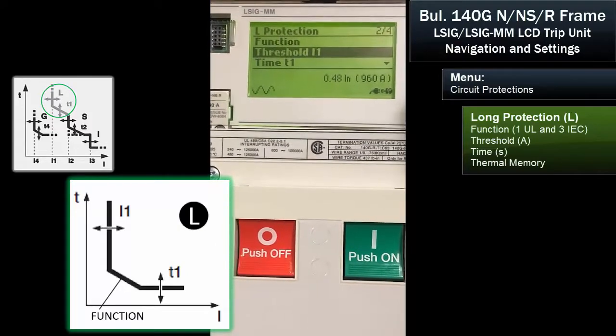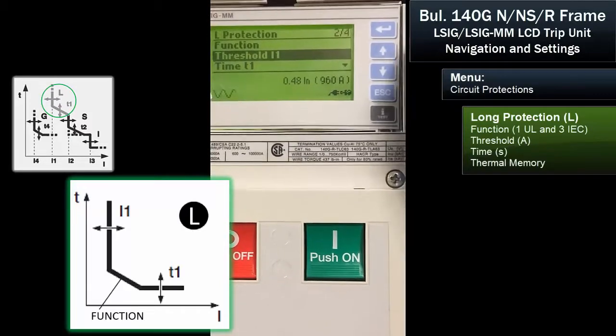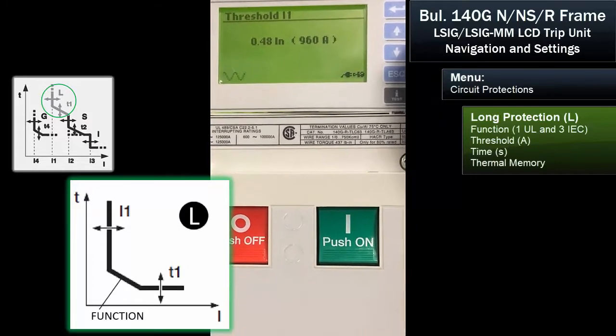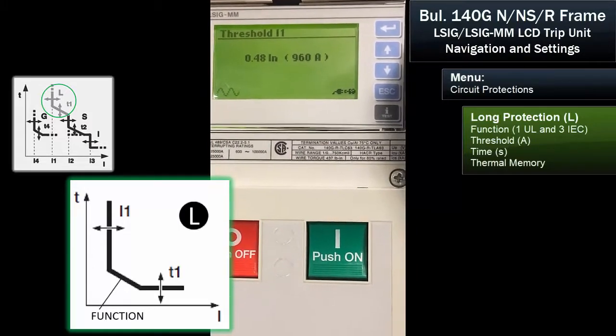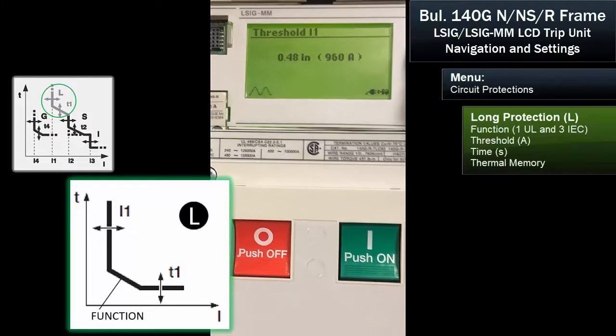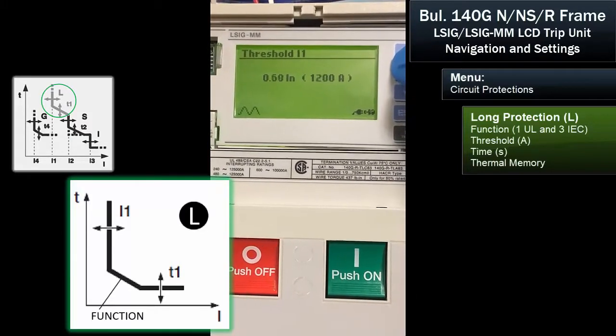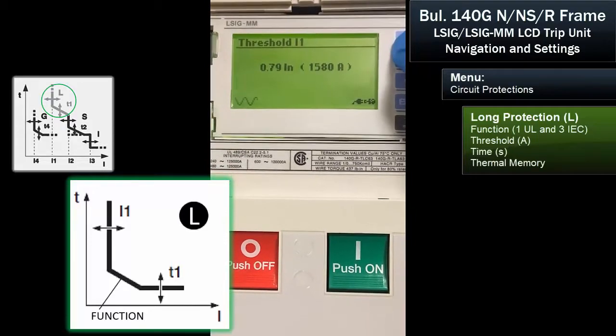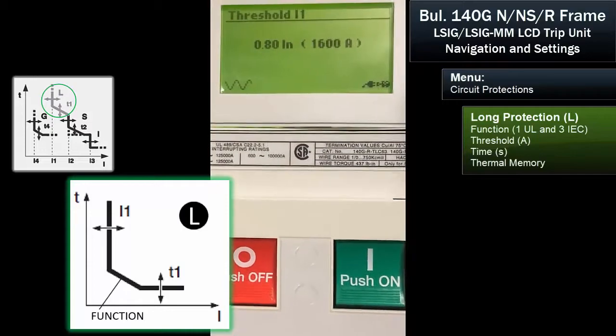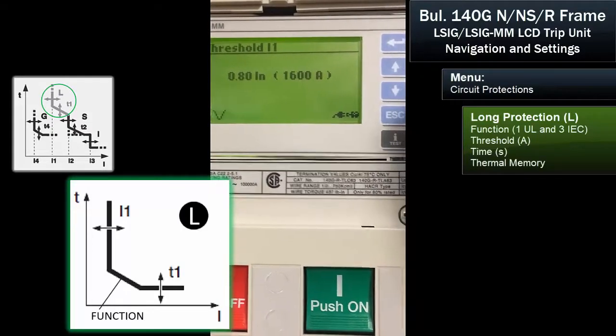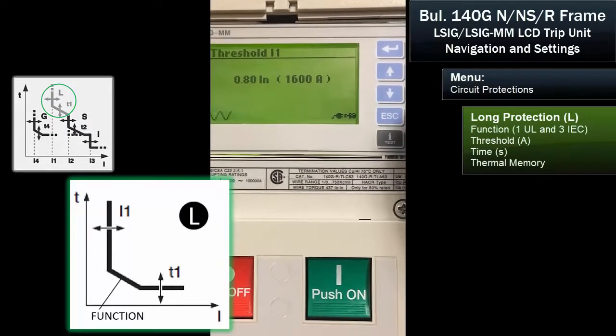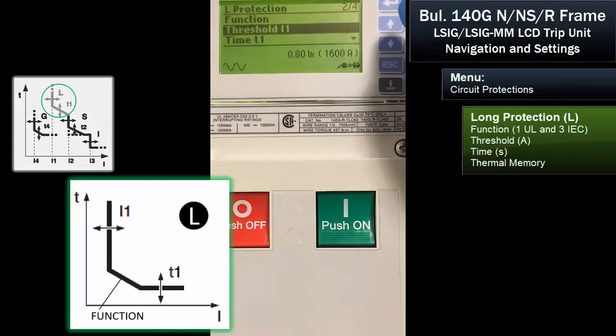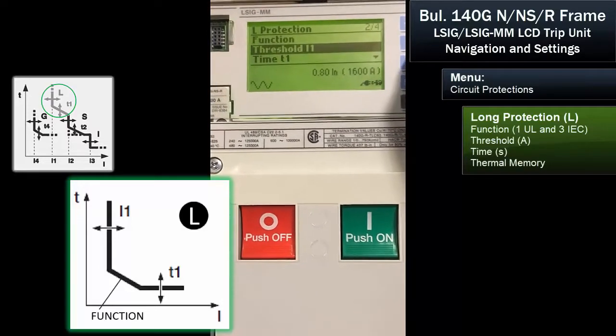Then we want to set the current threshold, I1. The breaker is adjustable from 0.4 to one times the setting. Let's set it at 80% as an example. This is a 2000-amp breaker, so at 80% of the rating, we've set the long time to 1600 amps.